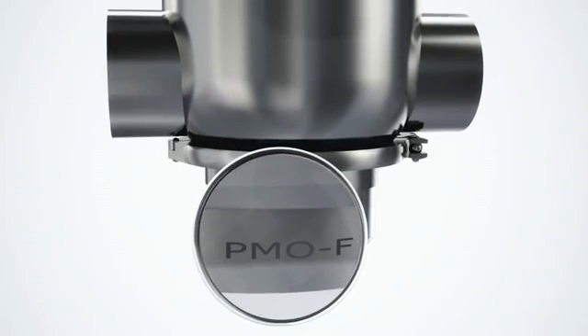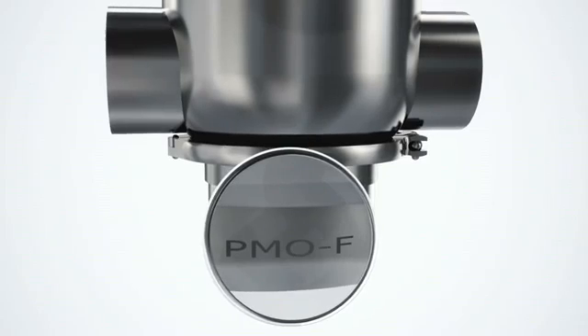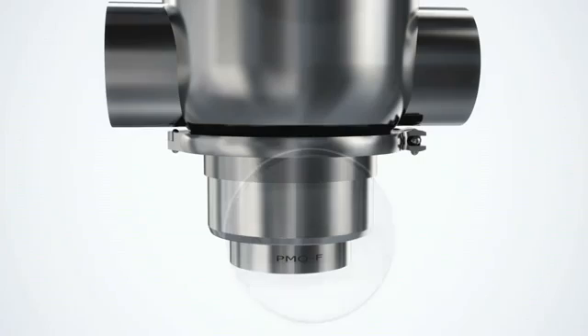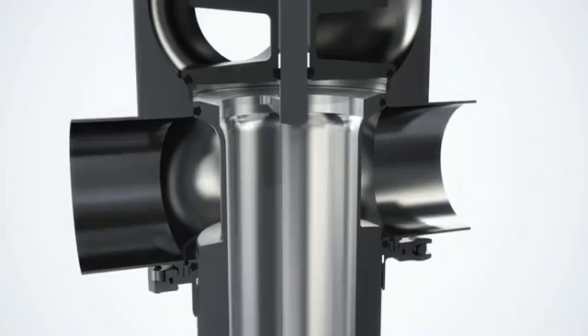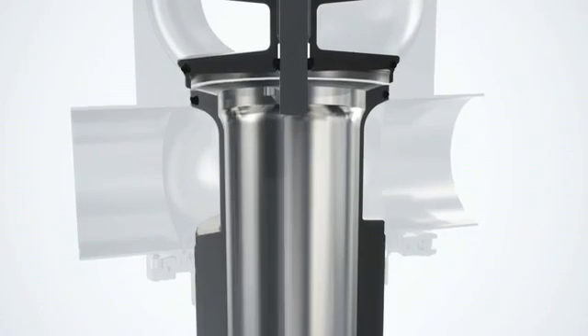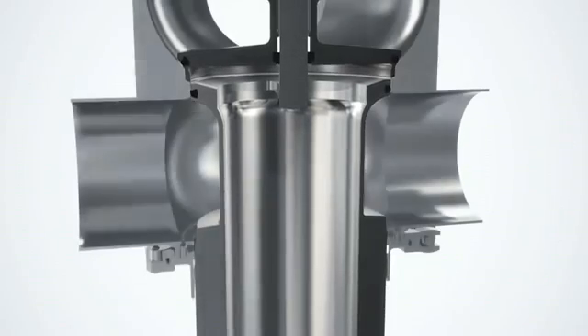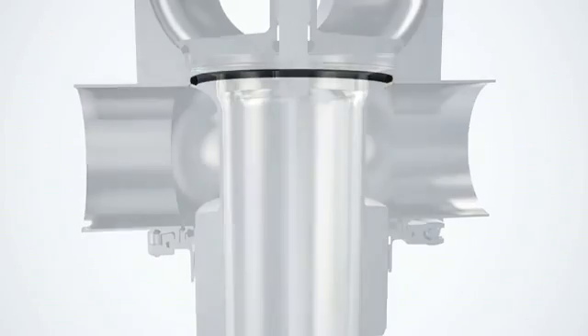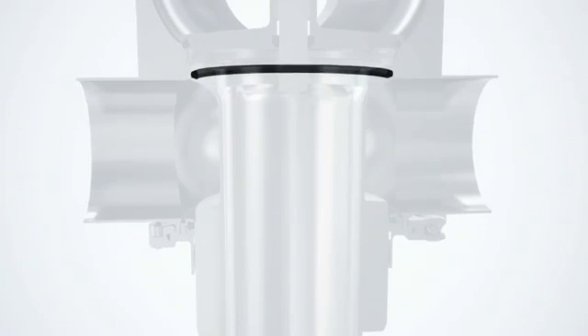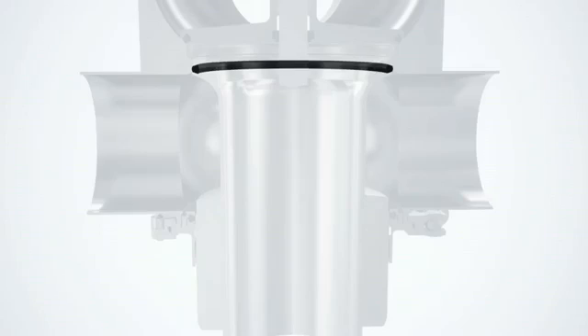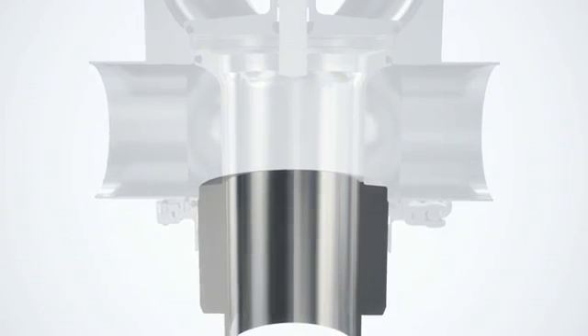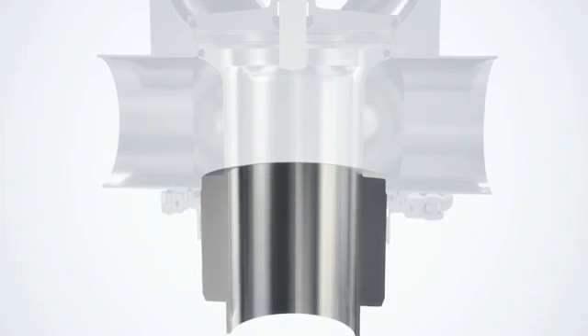Mix proof LP valve configurations are visibly marked on the external surfaces of the plugs. With its hygienic double block and bleed design, the mix proof valve has two independent plugs, each with a single seal. For long lasting operation, the lower plug has a radial seal. Hydraulically balanced, the plug provides reliable mix proof capabilities, even in the event of pressure shocks in the process pipe.